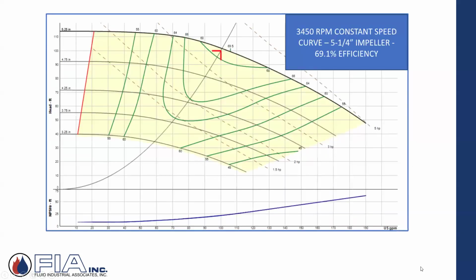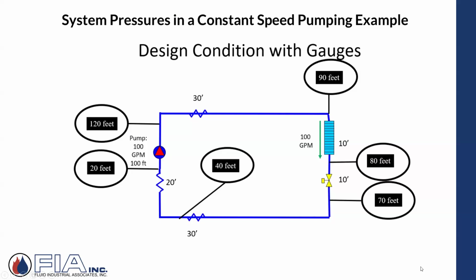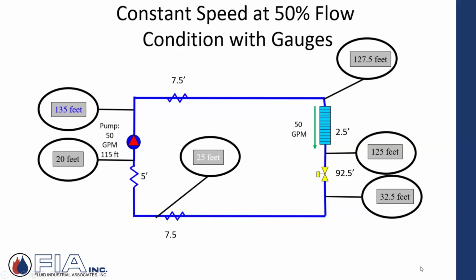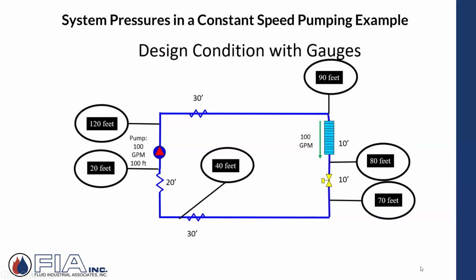Let's do a quick example together. And for those that are at home, I apologize for not having the wheel in front of you, but real quickly, this one circuit, which is supposed to represent a system, we're saying I'm pumping 100 GPM. And through this section of piping, maybe it's a terminal unit piping, whatever, it offers 30 feet of resistance. When I decrease the flow to 50, and why am I doing 50? Part load, valves closed. So I can take scale 5, or I can just do a calculation, or I can get on my app. But I could say when I was pumping 100 GPM, I was experiencing a 30 feet of head loss. So scale 5, 100 GPM opposite 30 feet of head.